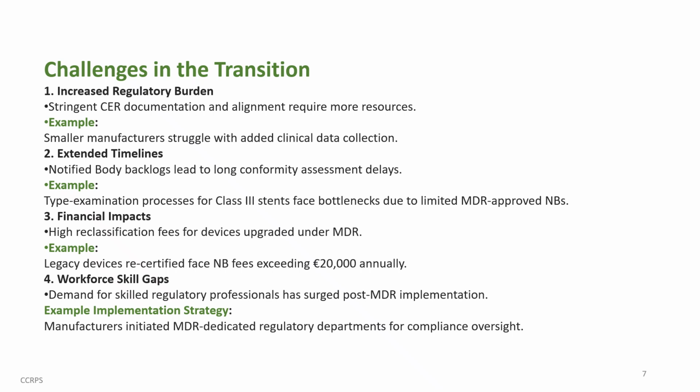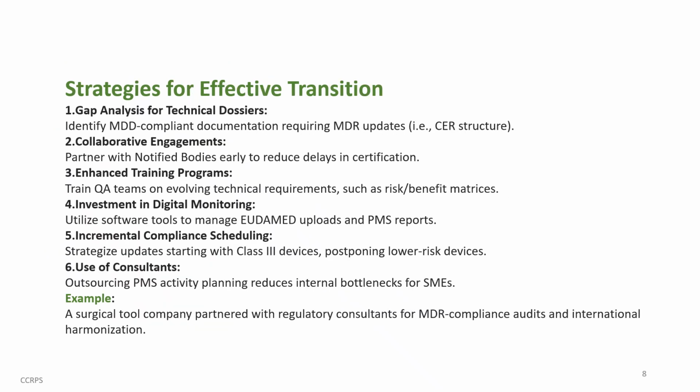Financial impacts: high reclassification fees for devices upgraded under MDR. For instance, legacy devices recertified face NB fees exceeding €20,000 annually. Workforce skill gaps: demand for skilled regulatory professionals has surged post-MDR implementation. Example: manufacturers initiated MDR-dedicated regulatory departments for compliance oversight.